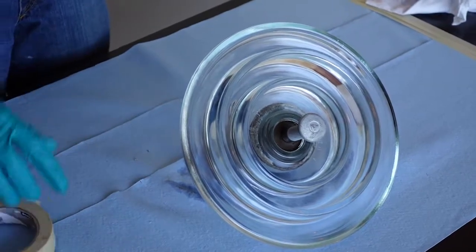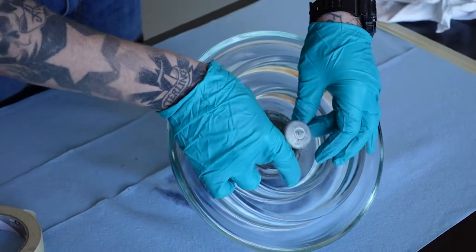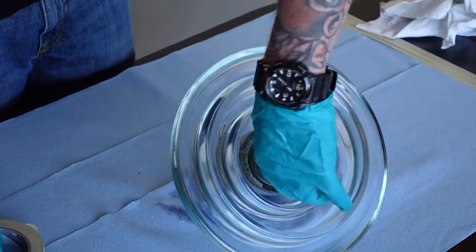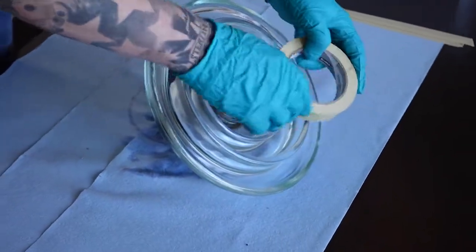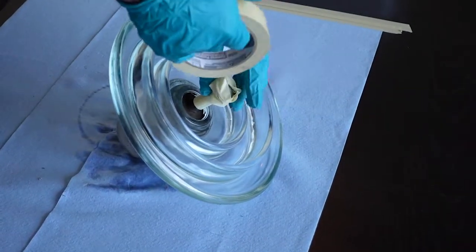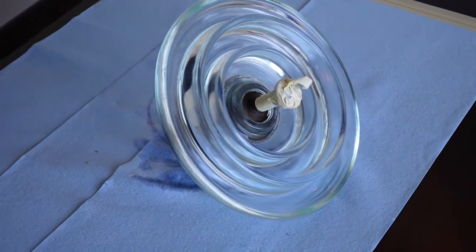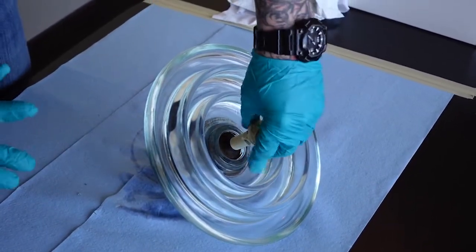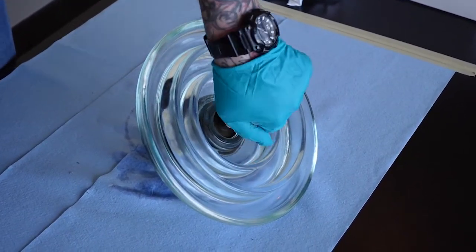Get a small piece of tape. We're going to wrap that just below the edge of that zinc sleeve and then continue our way up the top. This doesn't need to look perfect — basically we're going to want to do it so it's comfortable and can be done fairly fast if you have quite a few of these to do. As you can see, part of that zinc sleeve is still exposed — we're going to want to coat up about 80 percent of the way.